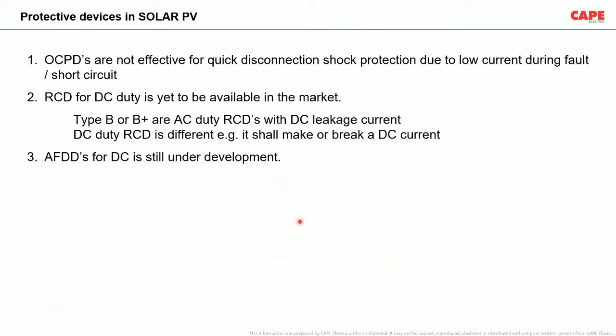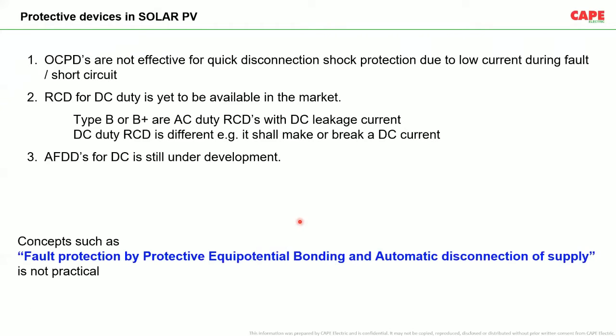The next important subject which you should always keep in mind is protective devices. Devices that work in an AC environment may not work in a DC environment, and most often may not be available. For example, OCPDs, overcurrent protective devices, are not effective for quick disconnection of shock. In an AC circuit, in a normal electrical installation, against electric shock, or fault protection, the concept of protective equipotential bonding and automatic disconnection of supply is the primary safety measure.